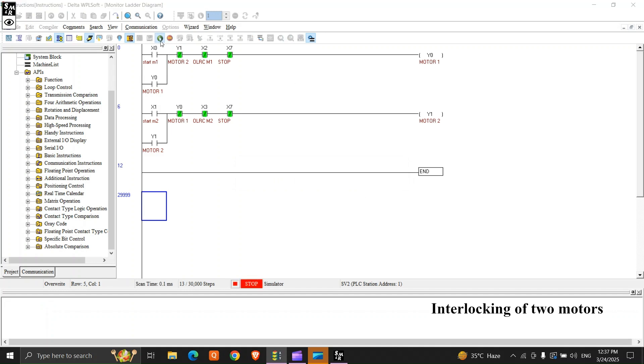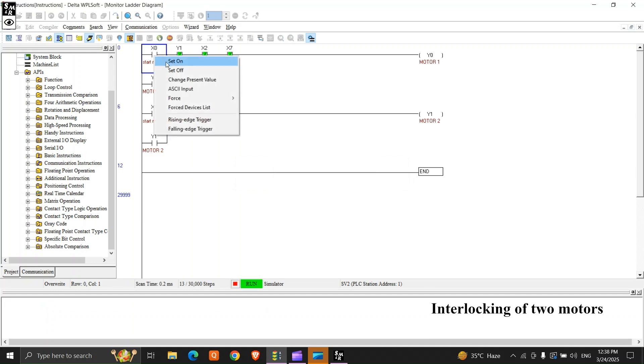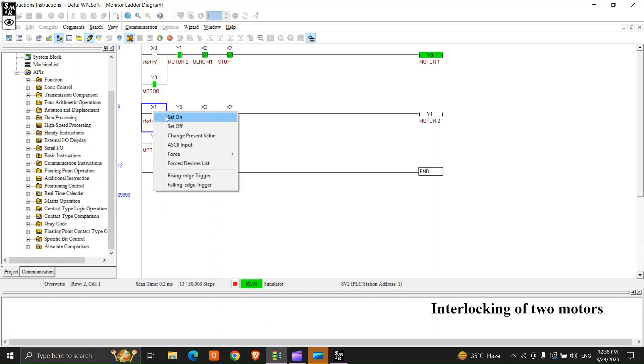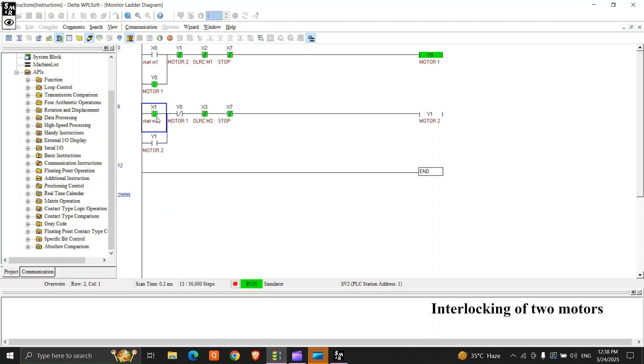So it's online. Start motor 1 — motor 1 is running. If we try to start motor 2, it's not running because we have placed an NC of motor 1, so that motor 2 will not start. This is known as interlocking of two motors.